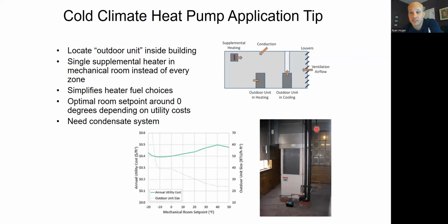Now, obviously, you can't do that indefinitely because the room gets hotter and hotter or colder and colder. So the room has to be connected to the outdoors. So they have this room sitting on the outside of their building. They have these louvers on the wall, and then the top of the heat pump, they duct to the outside. Not every heat pump can do this, but some models can be ducted a short distance. So they suck air in from outside, run it through their heat pump, and send it outside. So it's basically like the heat pump's outside, right? The heat pump's outside, but just sucking from this wall.